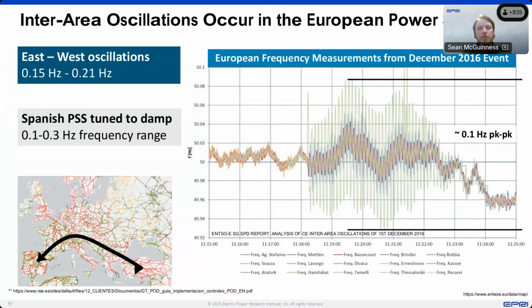You can see here that the oscillation kicked off. It had a roughly 0.1 hertz peak-to-peak oscillation range, and it moved around before it was damped out. It persisted for a number of minutes, about 5 minutes or a little bit less before it was damped out. So these are one of a number of known inter-area oscillation modes that exist. They've been very well studied and analyzed over time. There's also a north-south mode. So inter-area oscillations are not unusual in the European context, although active measures and studies have been taken to try and mitigate them.